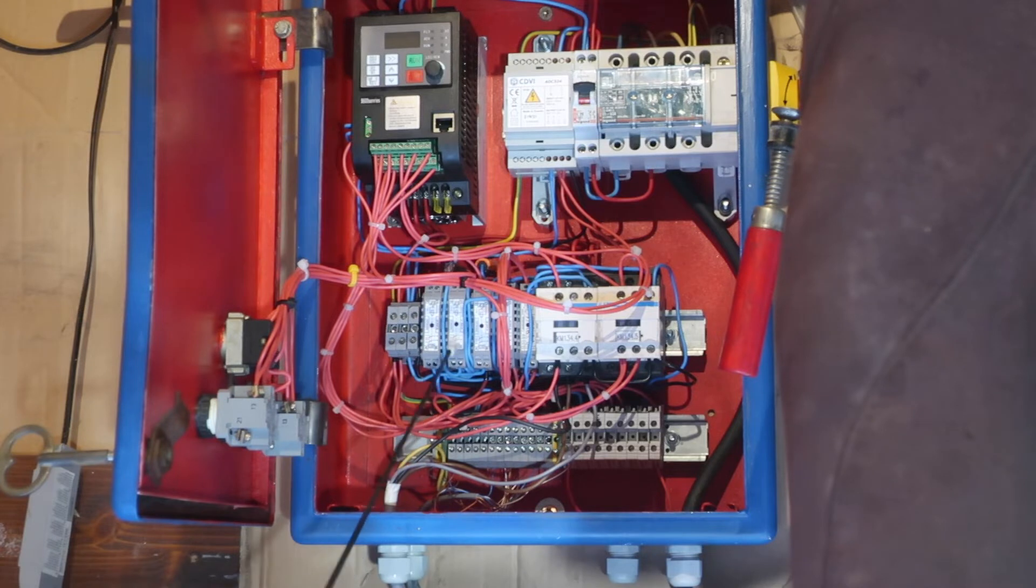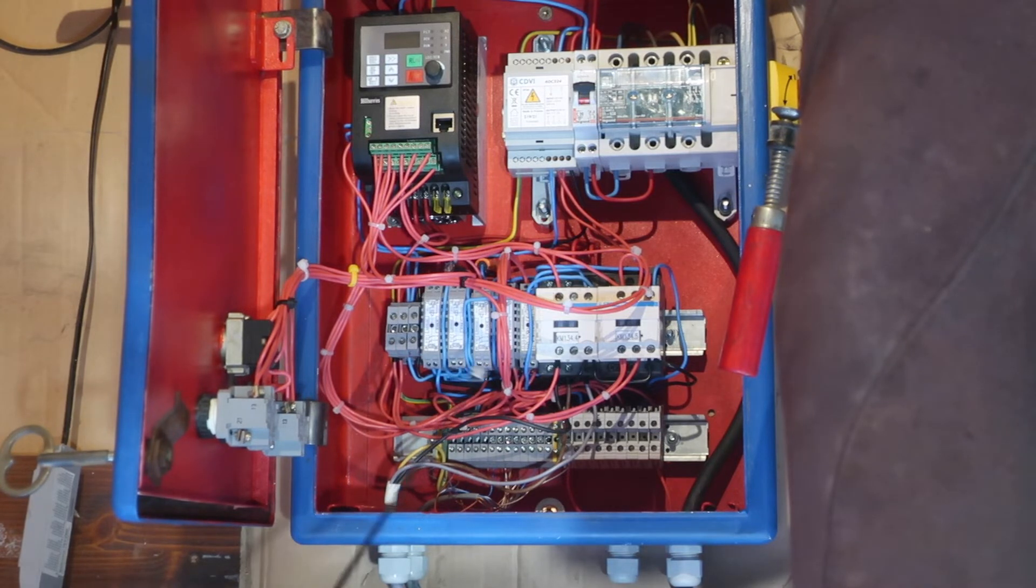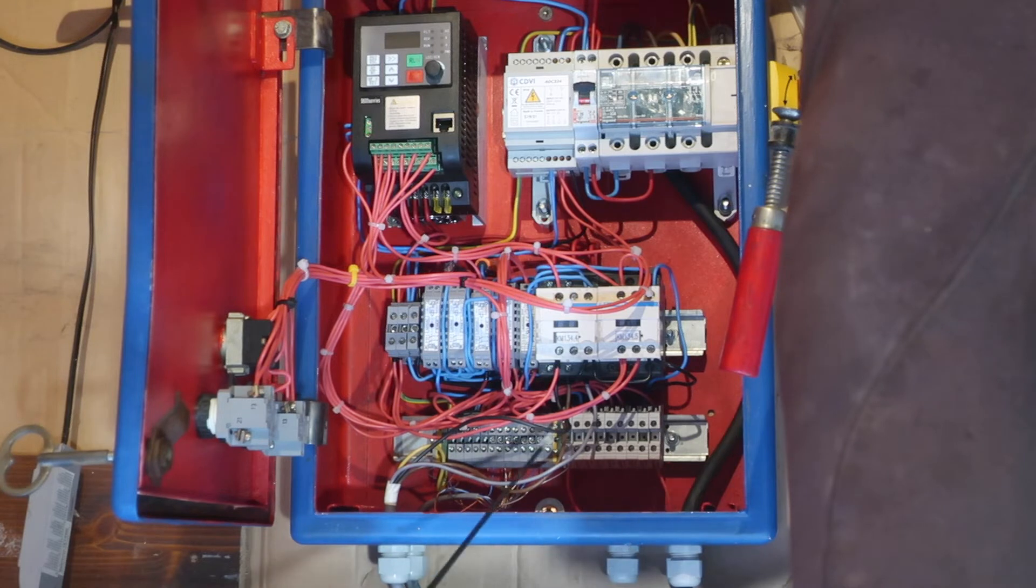This relay is followed by a relay which deals with, that's the inhibition relay, that's the machine selection relay, that's the motor selection relay. And then these last two relays deal with making sure that the controls on a machine that's not selected are not active. So basically it switches between two machines, switches the controls. The only control that's left active on everything is the emergency stop. And then at the bottom we've got a bunch of terminal blocks for the lathe and one for the milling machine, which are not connected at the moment.